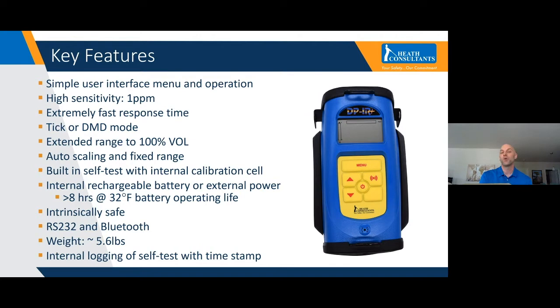It's two instruments in one. So you have that low level sensitivity on the 1 part per million side, all the way up to 100% gas and air. When it reaches that, it's all done via auto scaling. So there are no buttons or knobs to turn. It will automatically scale from the parts per million to the percent gas once it reaches that threshold, which is 10,000 parts per million or 1% gas. So once it reaches that, it'll automatically start reading gas and air.